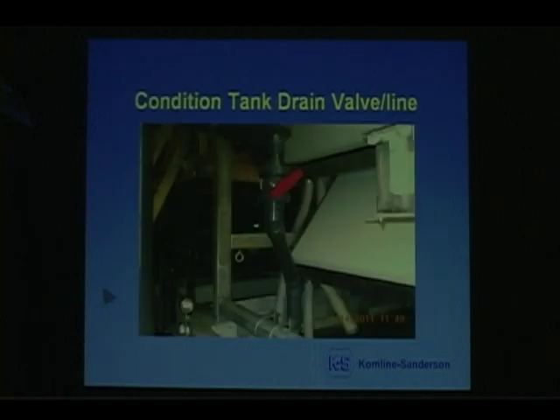We also installed a 4-inch drain line to drain that conditioning tank, or flocculation tank. Some people call it flocculation tank, some people call it conditioning tank. Whatever you want to call it, it's a tank, and you can drain it. One of the issues brought up by some of the operators is that the valve stays closed for a long period of time while they're operating, the sludge solids become solid in there, and the line will not drain. They recommend putting in a flushing line, so I got to talk to CDM and the contractor about putting a flushing line in that drain line.